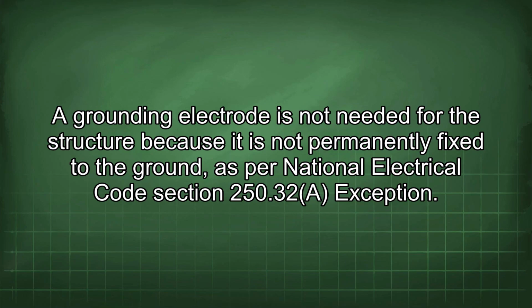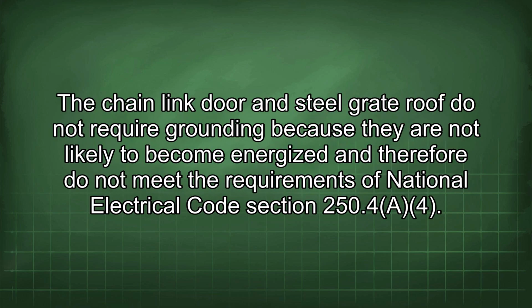A grounding electrode is not needed for the structure because it is not permanently fixed to the ground, as per National Electrical Code Section 250.32 exception. The chain-link door and steel grate roof do not require grounding because they are not likely to become energized and therefore do not meet the requirements of National Electrical Code Section 250.4.